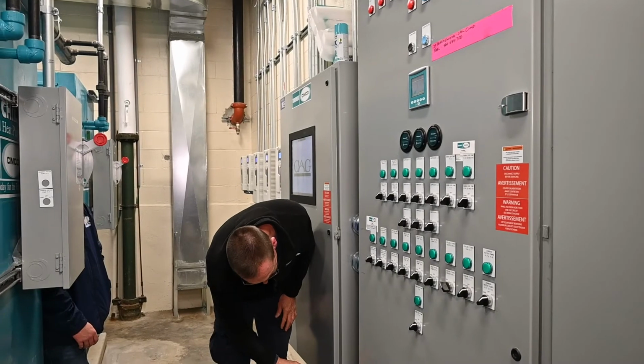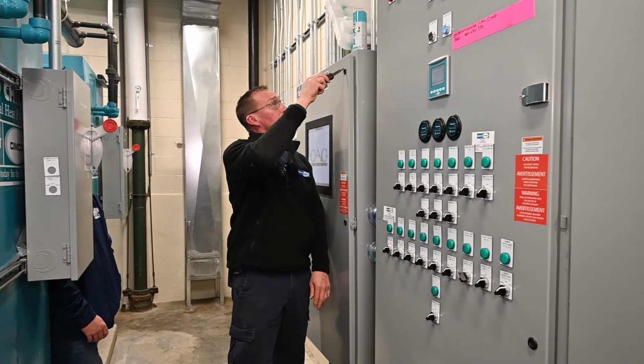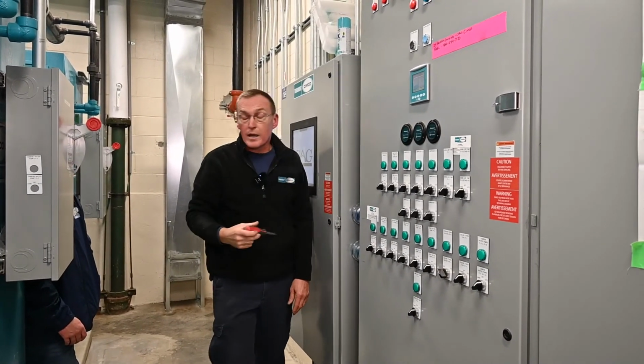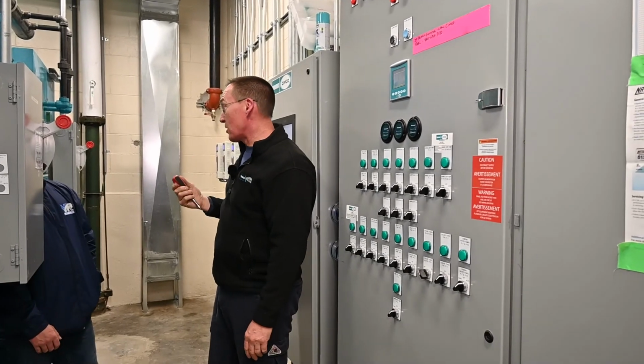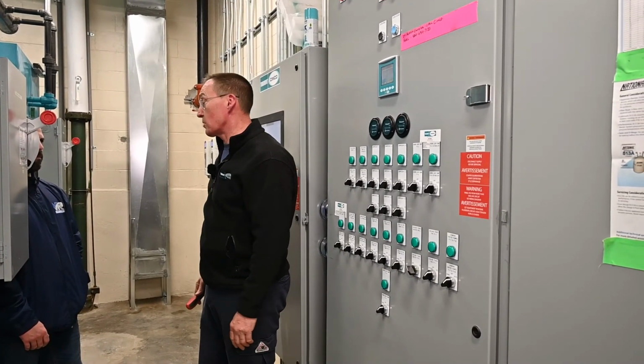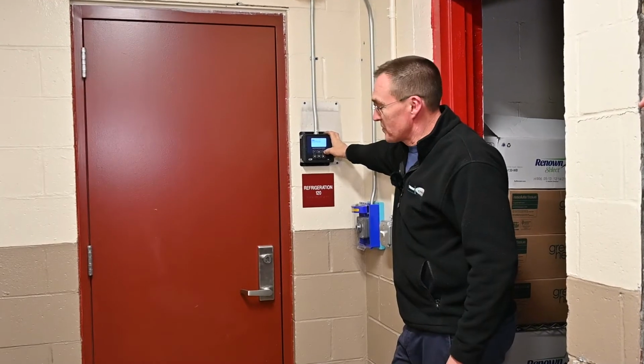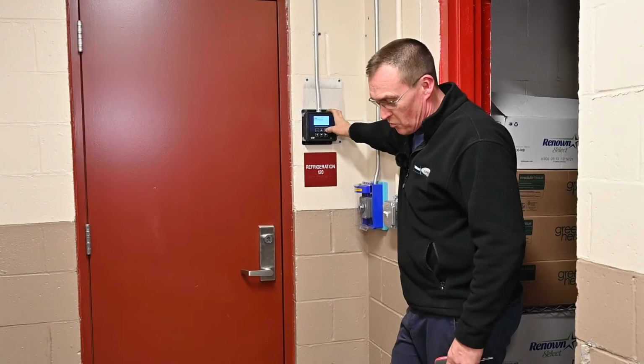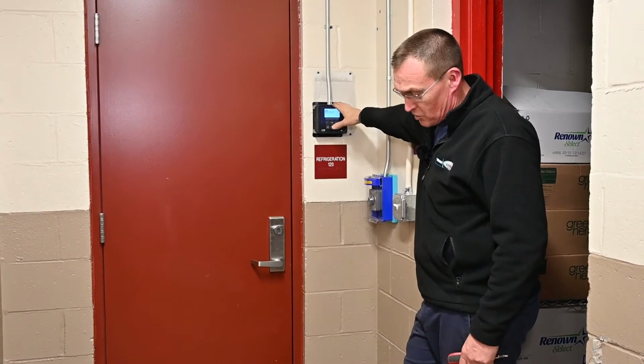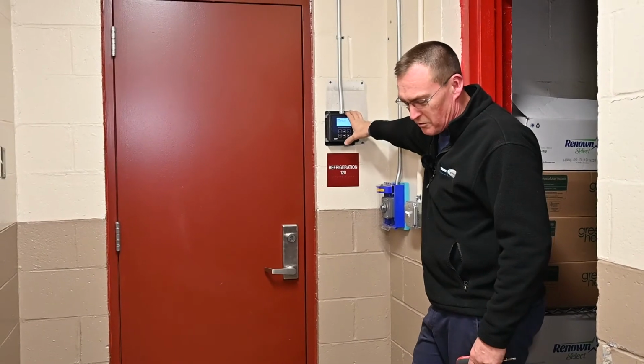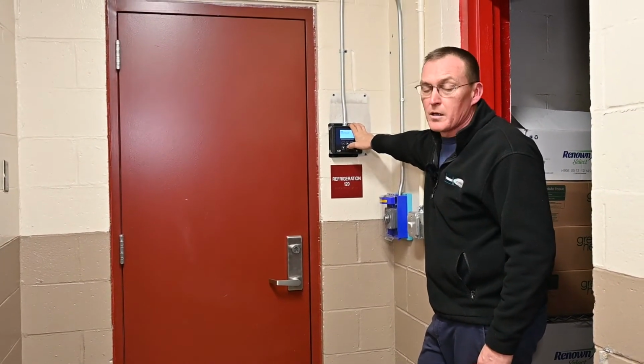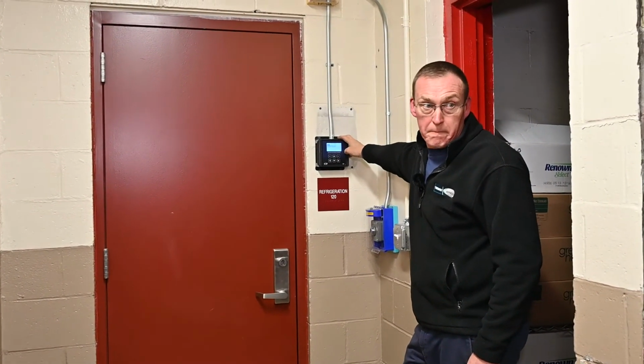Now let's go up top, and I'm going to go to the refrigerant detector and show you guys that alarm so you know what to expect when that's going off. So I'm going to test the refrigerant detection alarm so that you know what to expect if this detector goes off. This is a 0 to 500 ppm sensor. It triggers at 100 ppm.